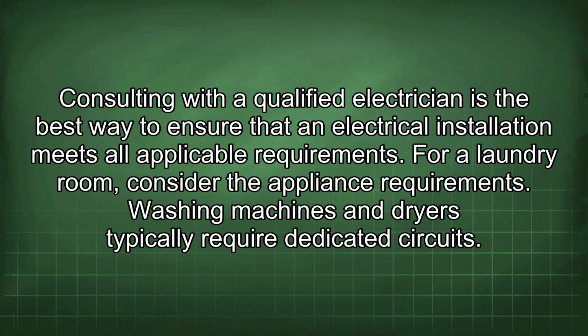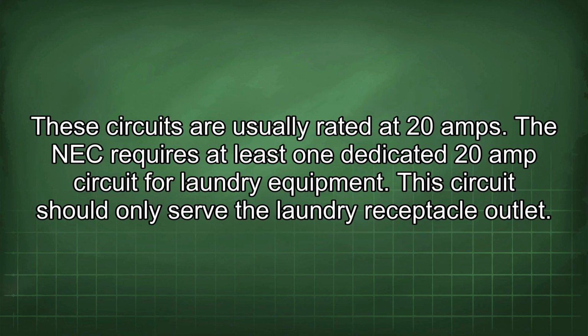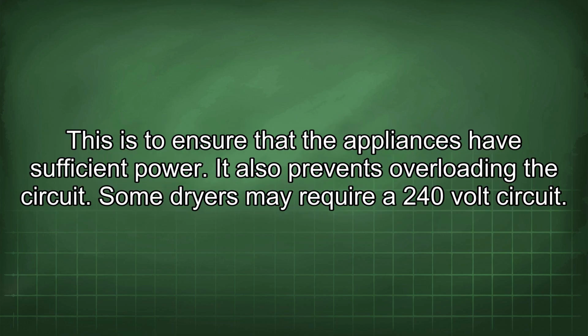For a laundry room, consider the appliance requirements. Washing machines and dryers typically require dedicated circuits. These circuits are usually rated at 20 amps. The NEC requires at least one dedicated 20 amp circuit for laundry equipment. This circuit should only serve the laundry receptacle outlet. This is to ensure that the appliances have sufficient power. It also prevents overloading the circuit.